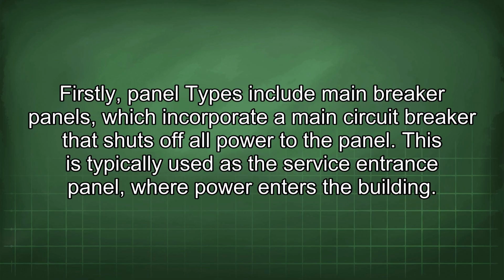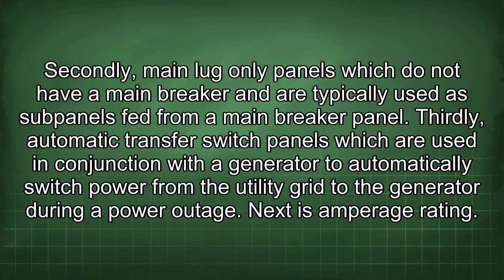Firstly, panel types include main breaker panels, which incorporate a main circuit breaker that shuts off all power to the panel. This is typically used as the service entrance panel, where power enters the building. Secondly, main lug-only panels, which do not have a main breaker, are typically used as sub-panels fed from a main breaker panel. Thirdly, automatic transfer switch panels, which are used in conjunction with a generator to automatically switch power from the utility grid to the generator during a power outage.